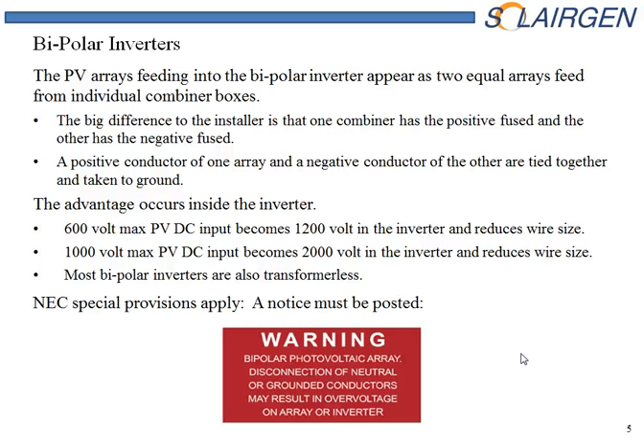The likelihood of you installing a bipolar inverter is pretty slim, but if you were to do this, there's a special label requiring the identity of this bipolar system. And if you're not familiar with the bipolar system, it's basically two separate PV systems tied into a single inverter, but one is grounded negative and one is grounded positive. And when they tie them together, they're essentially a series circuit, except they ground the positive and negative of one of each on the DC side, which brings it back to a parallel circuit. So if that ground were to be lost, we would have a high voltage, and this warning sign has to be put in place. Chances are you won't install one of these, so you may not have to worry.